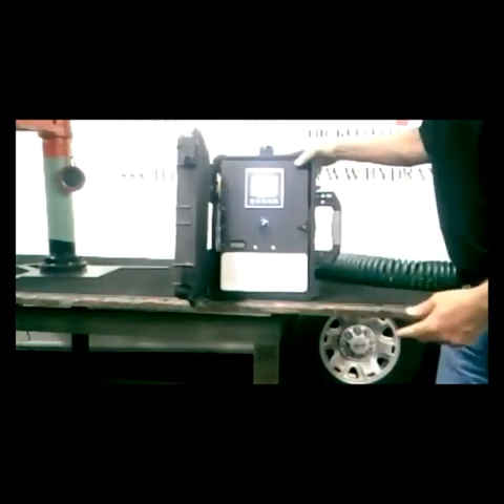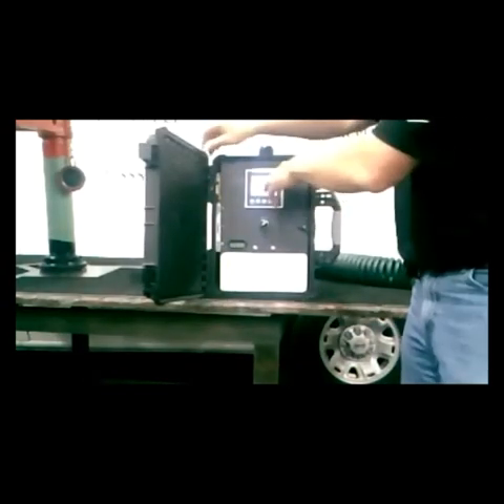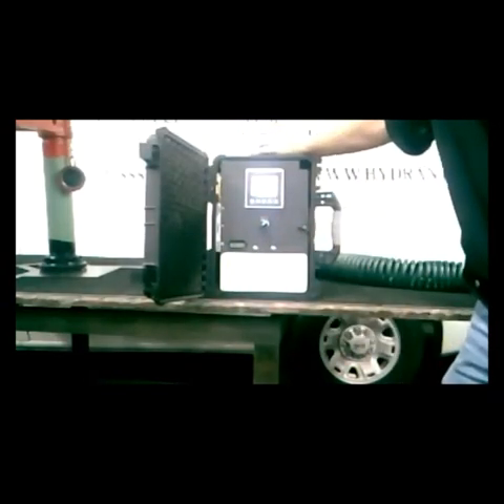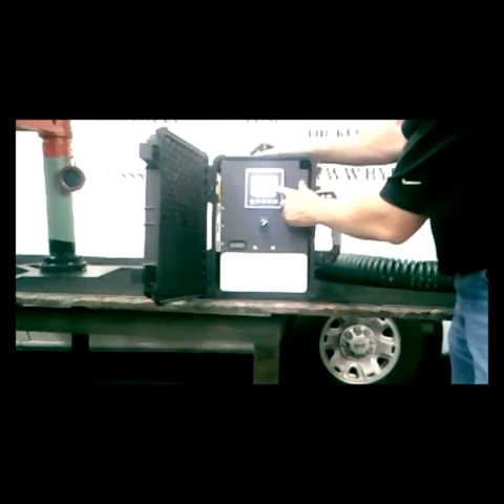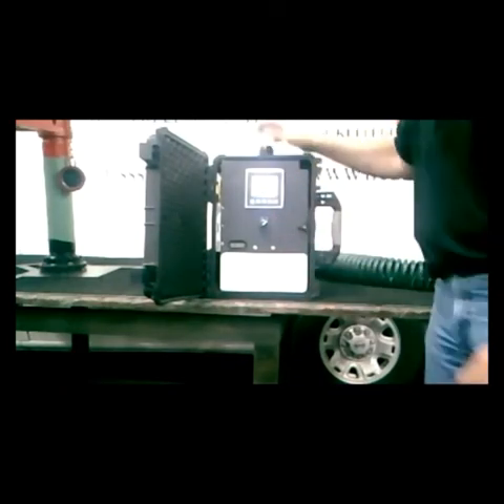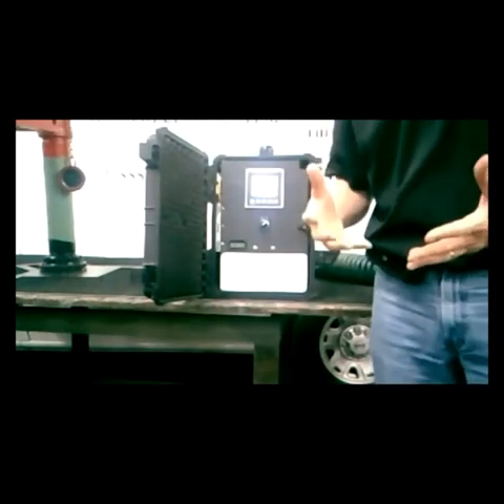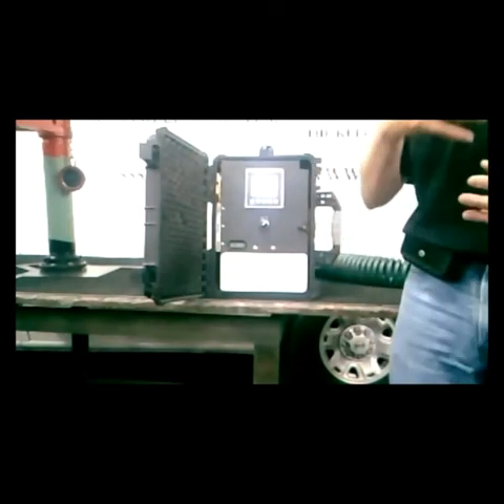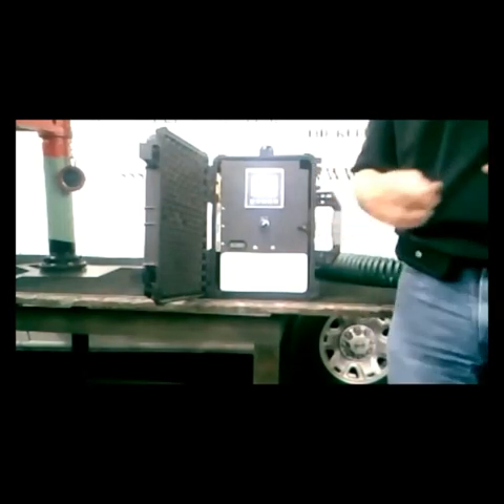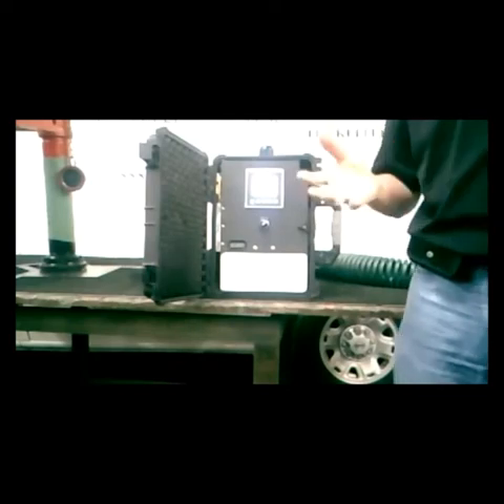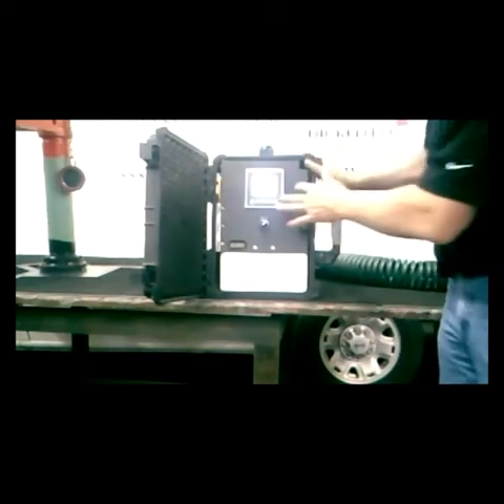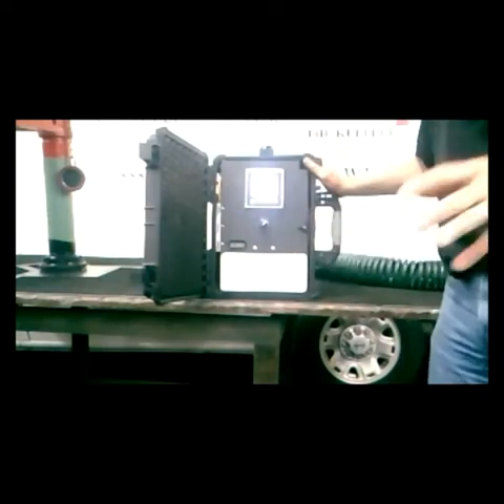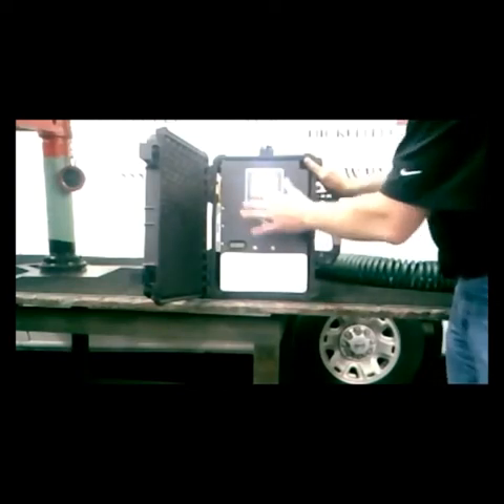On the screen there's a button you'll hit, and you'll punch in what hydrant I'm at. I'm at hydrant 635, I hit enter. Then you touch the screen and put in the residual or the NTU for turbidity you want to hit. I want to flush this hydrant until I hit a 1.5 residual and an NTU of 0.2. You hit enter, and then when you turn the hydrant on and start flushing, you hit this run button.